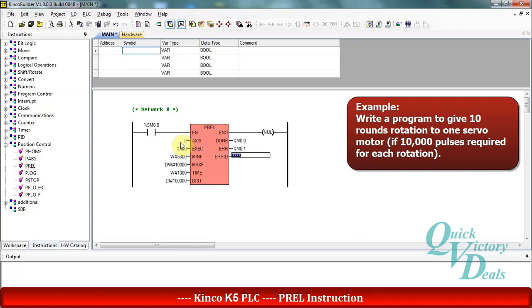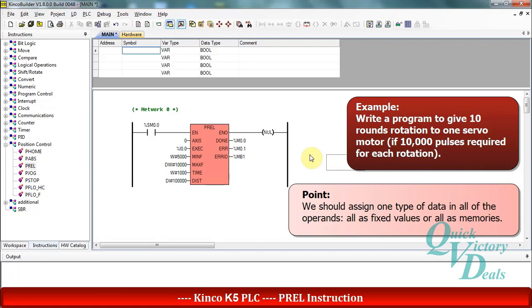The important point is that we should use one type of data for all of the operands in position control functions. For example, we should use memories for all of them or fixed values for all of them. We cannot use a mix of values and memories.